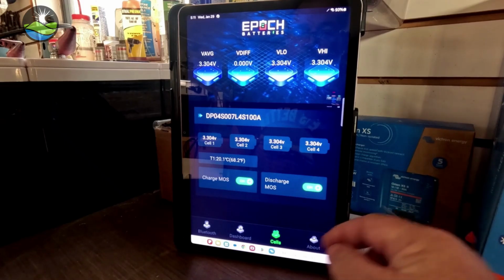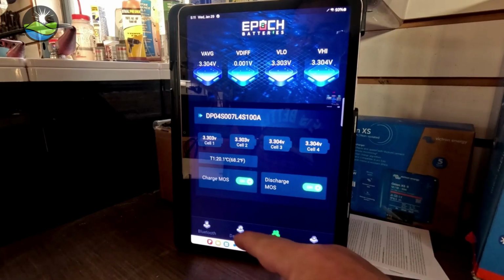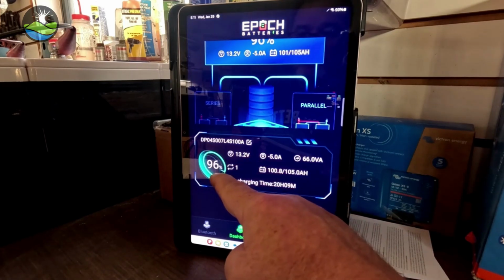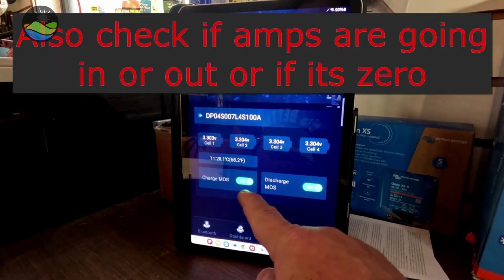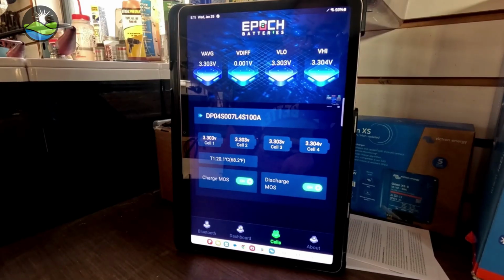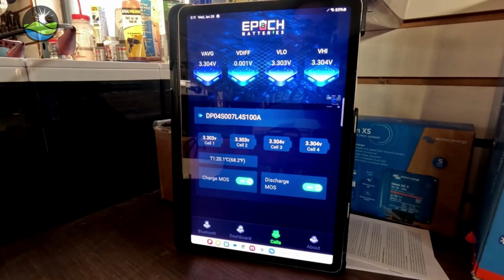As soon as you think something's not right, come here and check the actual voltage. Don't always look at SOC. Check the actual voltage, check the state of your charge and discharge MOSFETs. That's going to tell you a lot about what they're doing and what you should be troubleshooting next. I can tell you about 999 times out of 1,000, it's typically the customer's equipment, the charger's not set right, or a fuse was blown during installation or something like that. So it's extremely useful to know the position of your charge and discharge MOSFETs when troubleshooting.